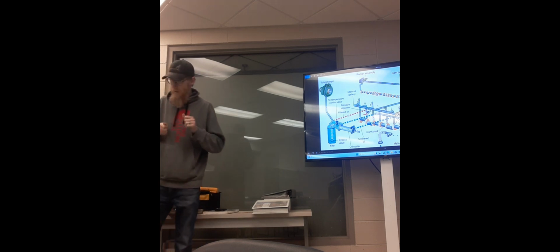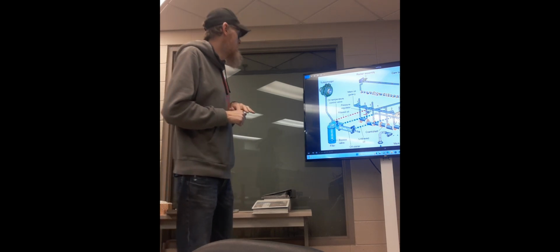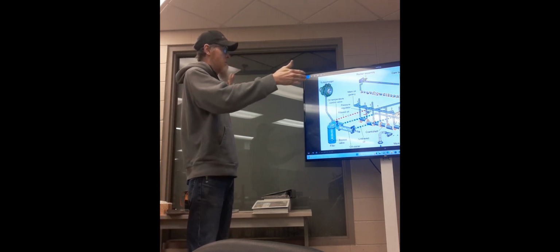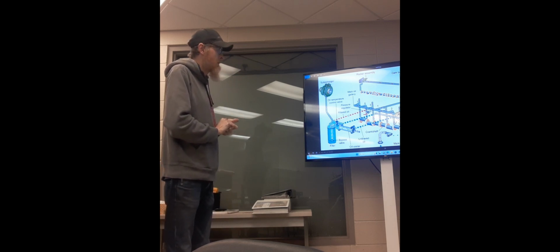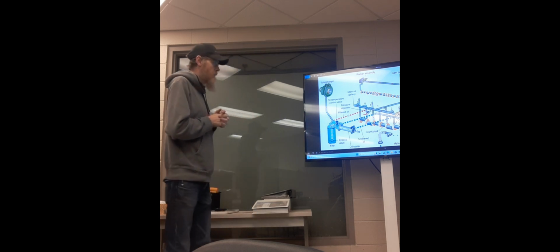So the first thing I wanted to look at was an image that should be labeled 10-1, and it's just showing us an entire oiling system, just a generic diagram of our oiling system and how that works. And we're going to kind of jump off from here and talk about the different components that make up the entire lube oil system. So ultimately, we've got an oil pickup tube. That's where our inlet into the oil pump is going to be.